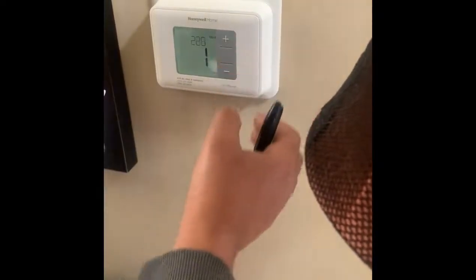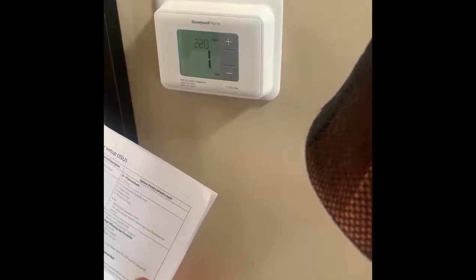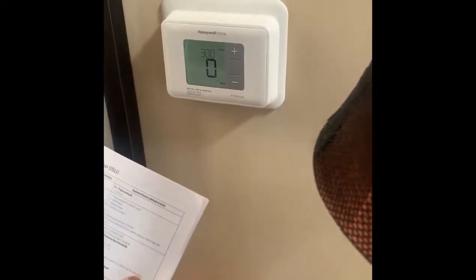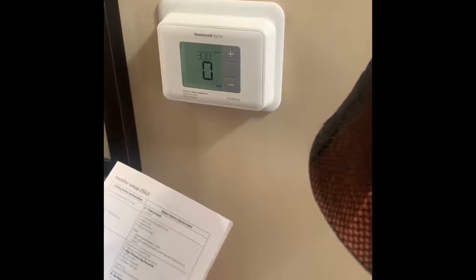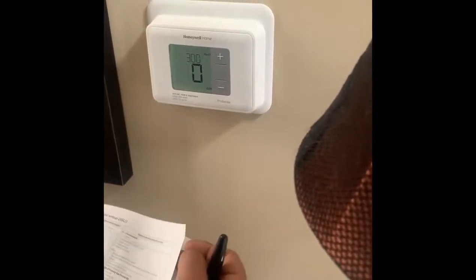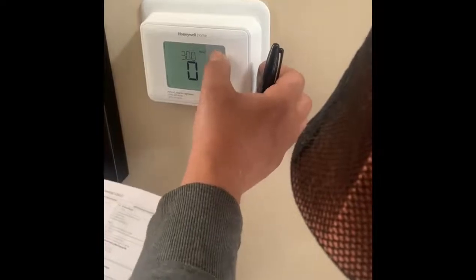Next is setting 220: two-stage compressor — that's fine. Setting 300 is system changeover: manual or automatic. Let's leave it manual, otherwise it won't go on and you'll get hot inside on a winter day. So zero is fine.